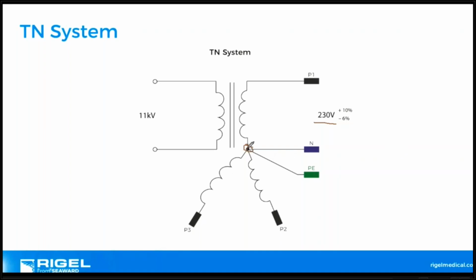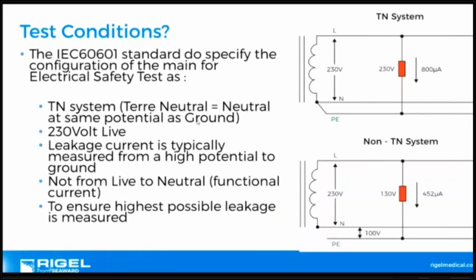But you need, at least as far as 60601 is concerned, neutral and earth to be common, because if you have any fault condition and these two are separated, there's nowhere back for the current to flow. So you're not correctly measuring current. And I'll show you that in the next example. So 60601, the standard specifies that you must do all of your testing on the TN system. It's the same with NFPA 99 because it uses the same type of measurement. 62353 does have solutions to test on non-TN systems, like the alternative method. However, to correctly measure your leakage currents, you really must be on a TN system.